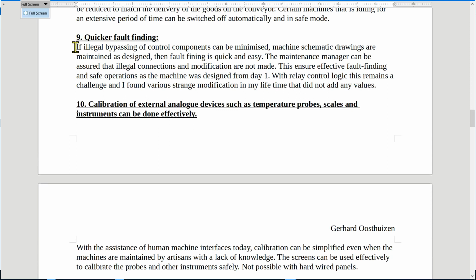Now, if illegal bypassing of control components can be minimized, and machine schematic drawings are maintained as designed, then fault finding is very quick and easy. The maintenance manager can be assured that illegal connections and modifications are not made. Now, this ensures effective fault finding and safe operation as the machine was designed from day one.